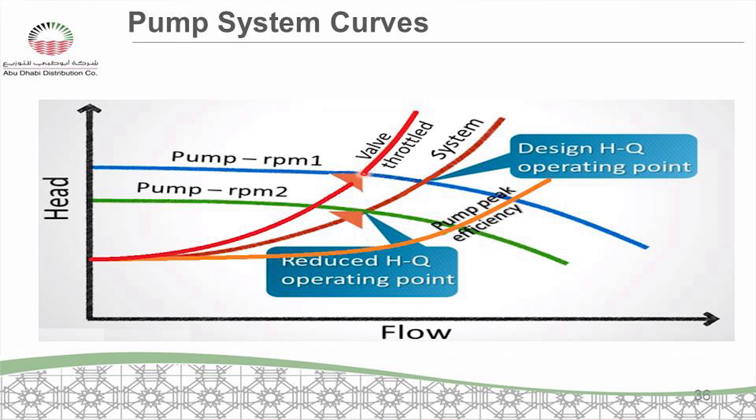What is happening for all pumps: the pump maximum efficiency is always beyond the design duty point. The duty point by the manufacturer is Q against H — this is the duty. But when you look at the efficiency curve, you will find the maximum efficiency is here. So if you go and work there, it is even better — you are having higher efficiency, lower energy consumption, and less pressure. All of this is the trick, the principle for optimizing.